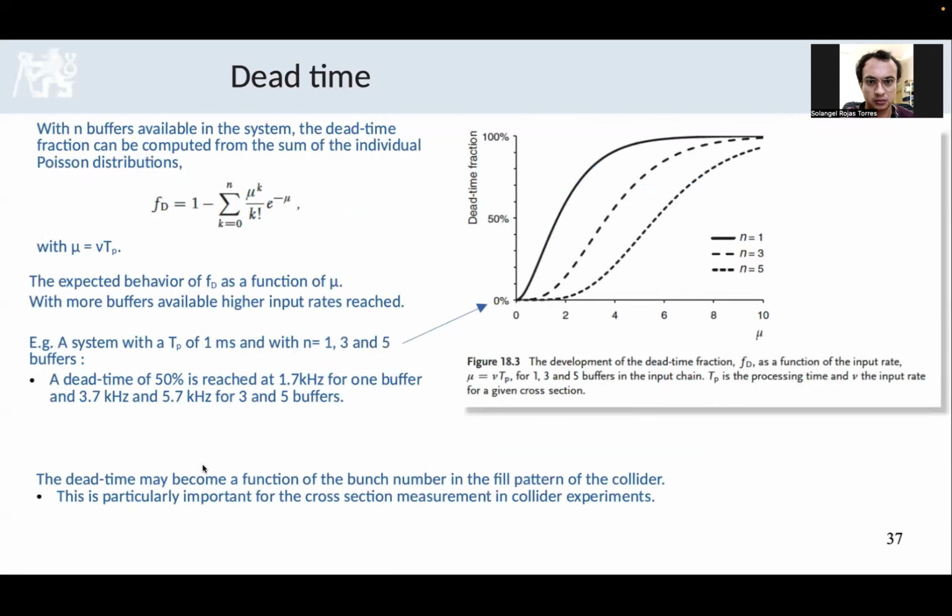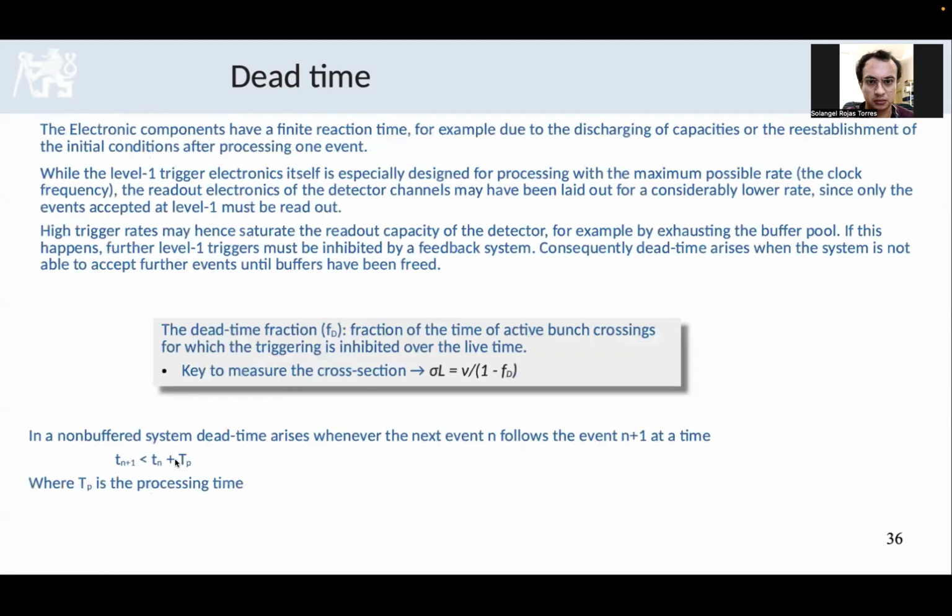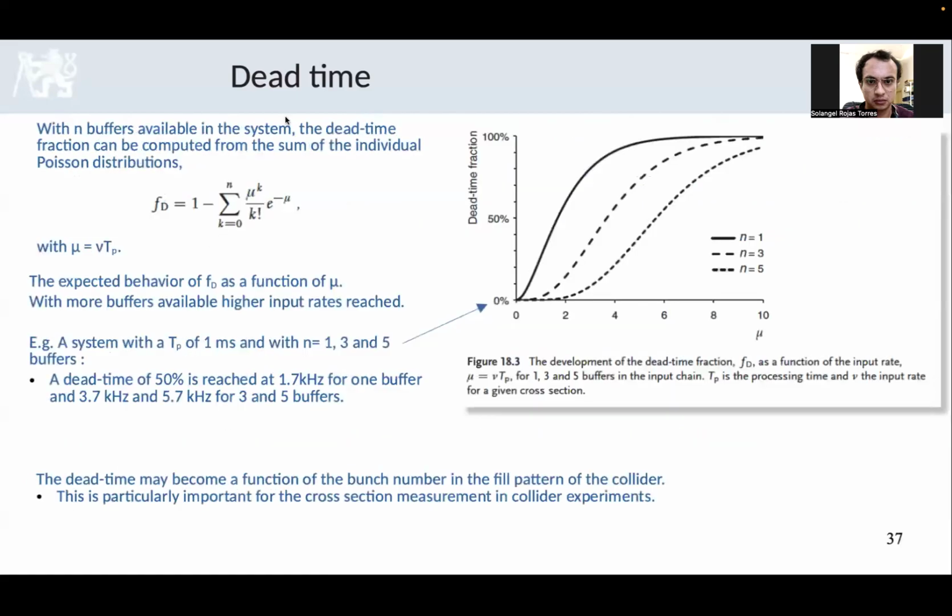And well, this is the lowest timing that you can have for this specific detector, but you can reduce the dead time by using buffering.